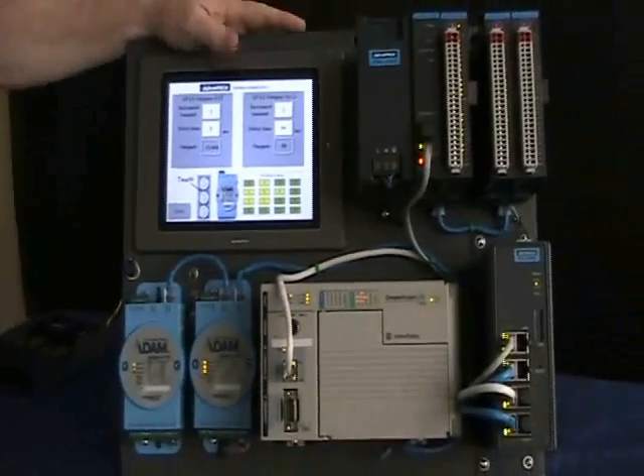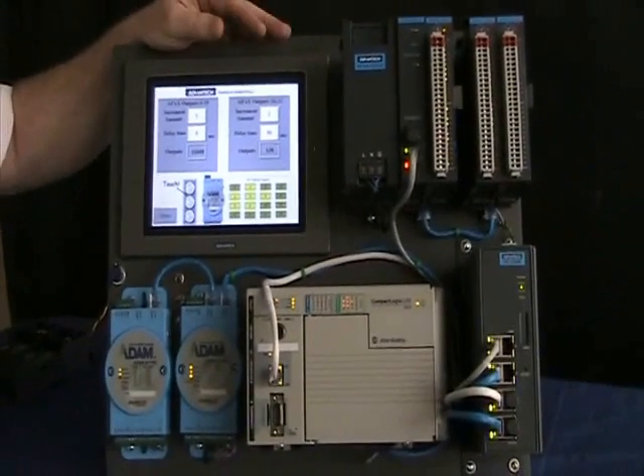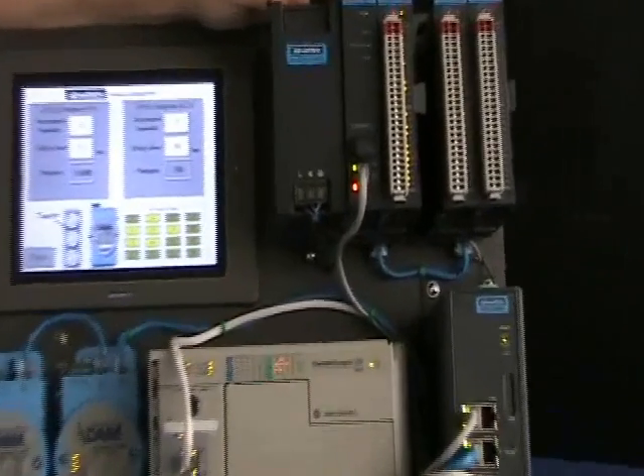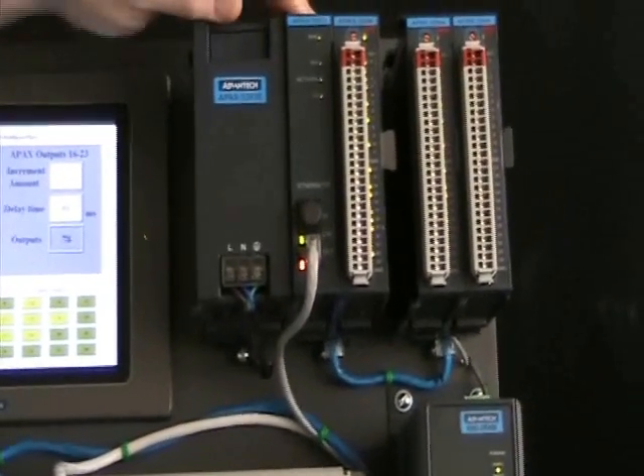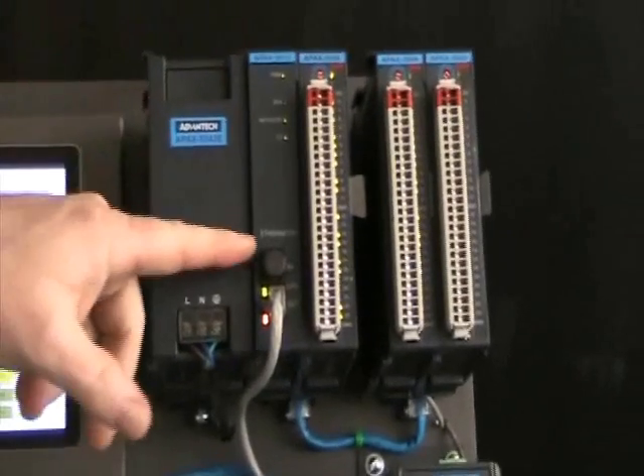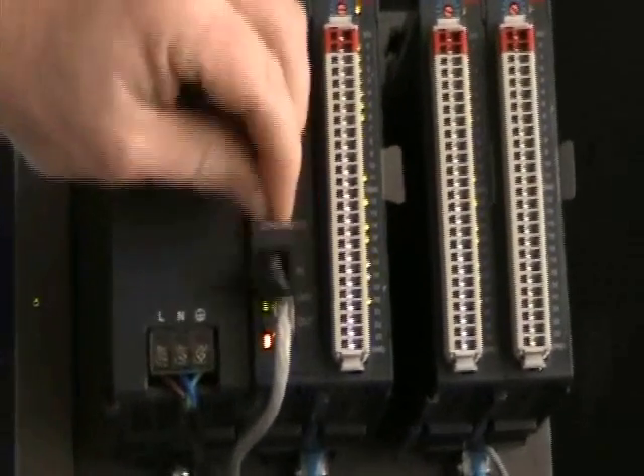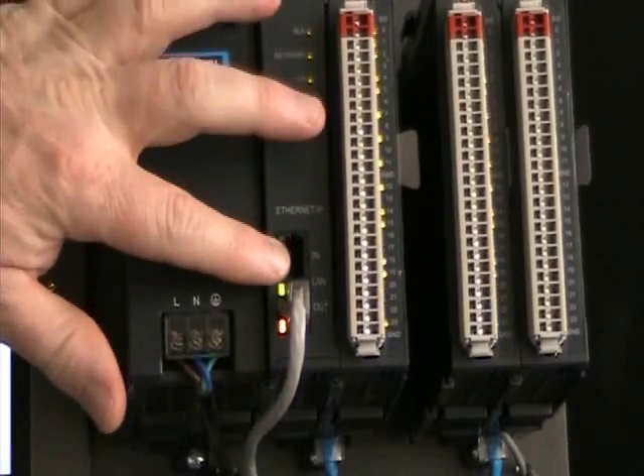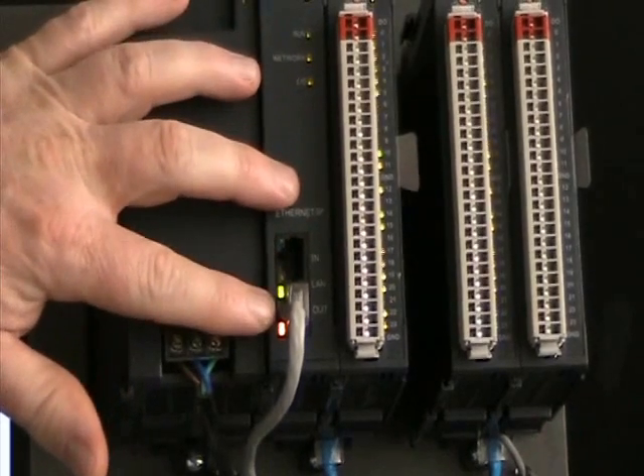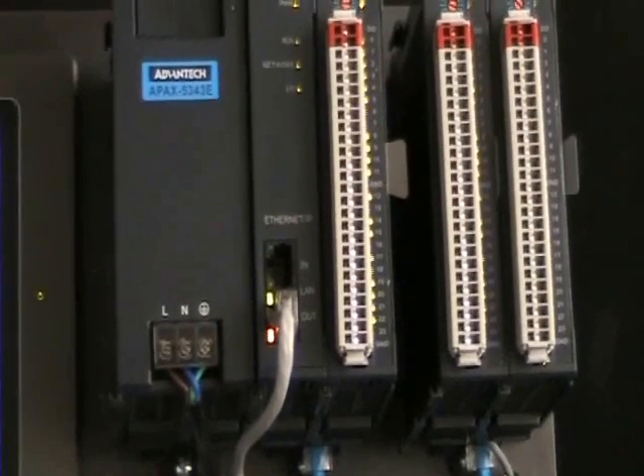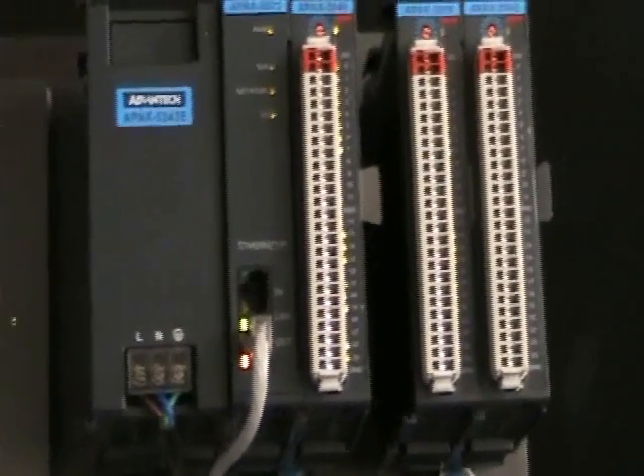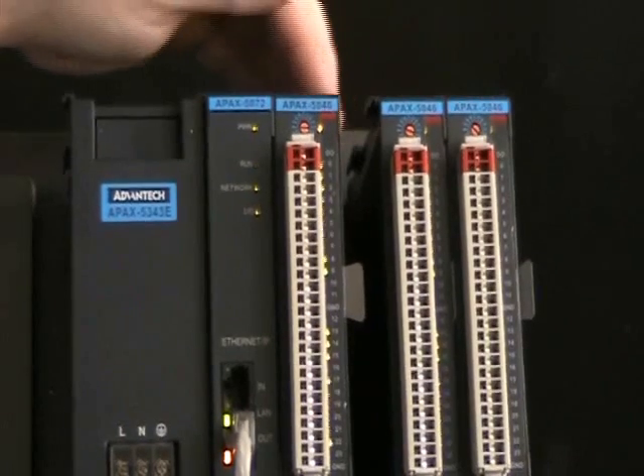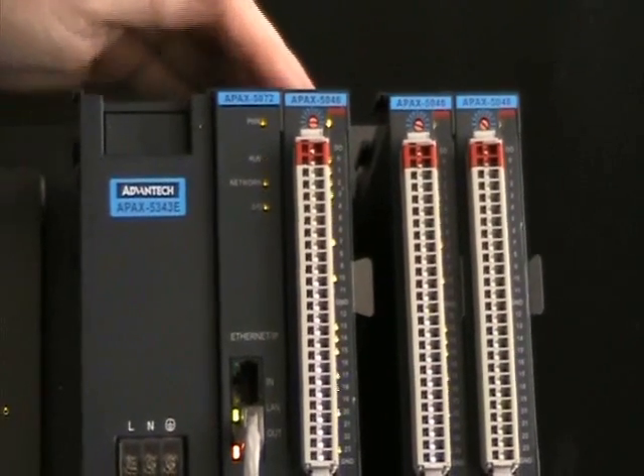The next piece that we want to talk about is the APAX 5072. This is Advantech's Ethernet IP coupler. It's a communication coupler that has two ports and is Ethernet IP conformance tested and approved. This coupler is connected through a backplane to these I.O. modules. These are APAX 5046 digital output modules.